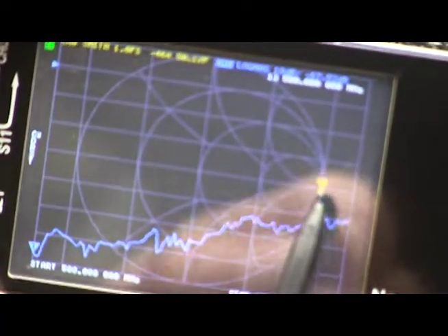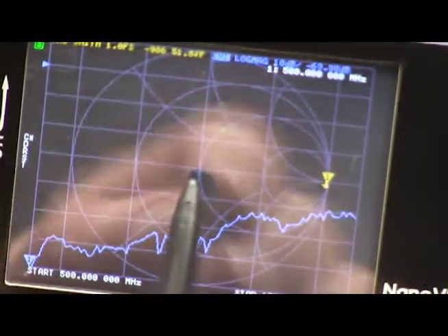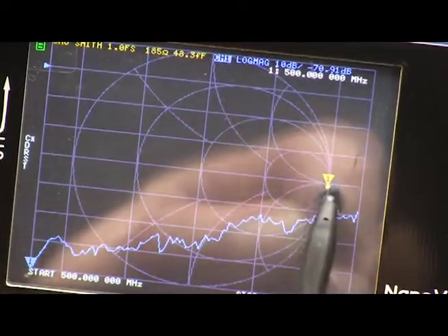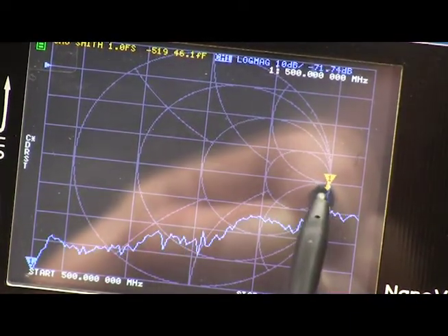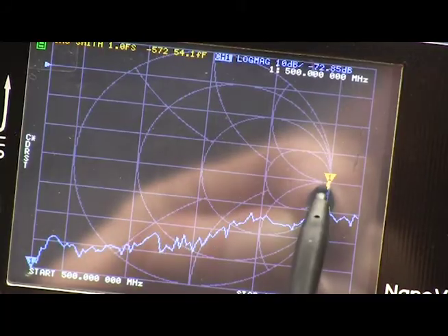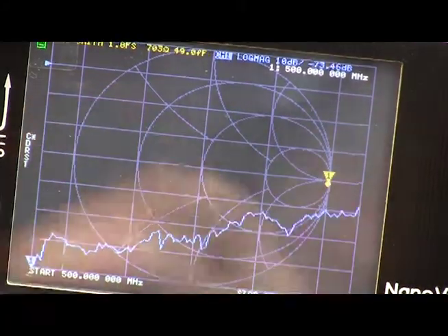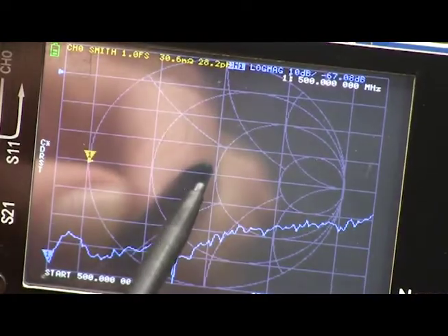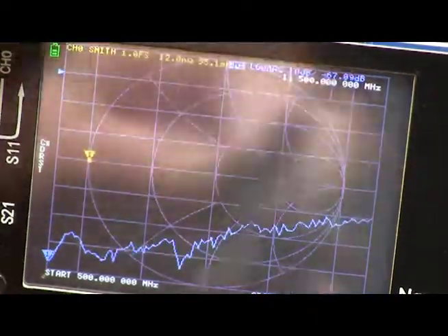So if we notice, all of a sudden, our signal has moved all the way over to the right here. And so that's exactly where we would expect for a Smith chart. It would stay in the center for impedance matched, and it would move all the way over here for an open. A short should move us all the way to the other side. So let's apply our short. We'll be looking for the one with the metallic pin center. And now we look at it, and now we're on this side of the Smith chart. Every time you calibrate, you should put on a 50 ohm, an open, and a short, and make sure it looks the same.